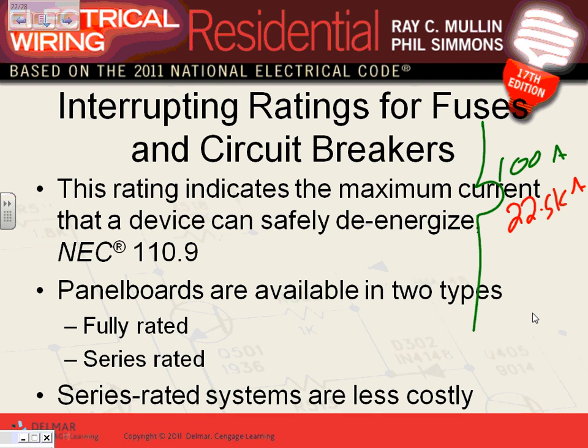They can be molded like these ones that you're looking at, or you're going to see later on when we go 2,000 amp, they can be a foot by a foot by a foot draw out circuit breaker. Imagine a foot by a foot by a foot, 3-dimension, big block with an electronic brain in it, that you can pull in, pull out, put it on the table and fix it. We'll talk about these as we go through. Any question, guys? Okay, I'm going to give you a quick break, and then I really want to hit the fully rated, series rated panels.